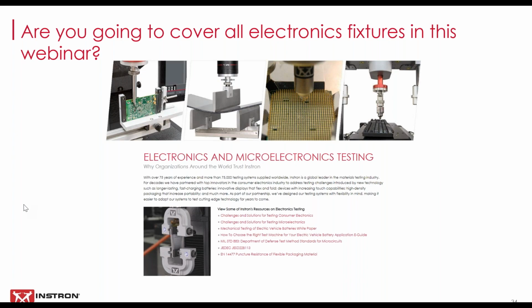Hey, Theresa, I just want to answer one last question. Sure, Charlie, go ahead. A very simple, quick one. Can a specimen centering device be attached to any manual grips, so non-pneumatic? I wouldn't say any manual grips, but yes, it can be added to some of our manual grips. Our advanced screw side action grips have specimen centering available for them. So you can reach out if that's something you're interested in.